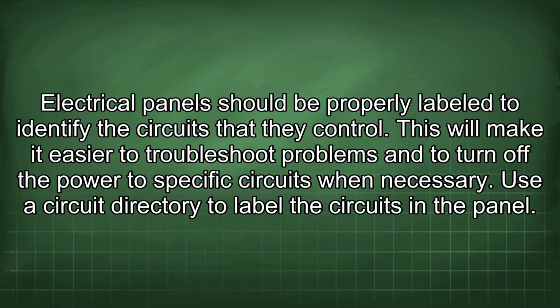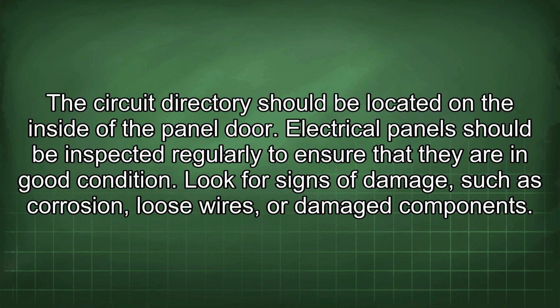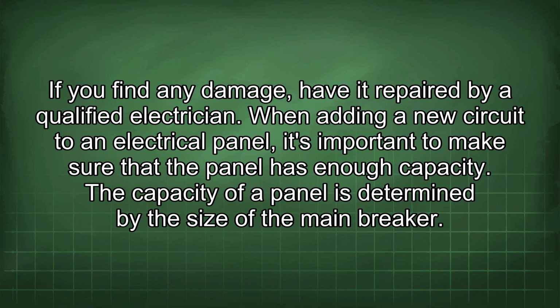Electrical panels should be properly labeled to identify the circuits that they control. This will make it easier to troubleshoot problems and to turn off the power to specific circuits when necessary. Use a circuit directory to label the circuits in the panel. The circuit directory should be located on the inside of the panel door. Electrical panels should be inspected regularly to ensure that they are in good condition. Look for signs of damage such as corrosion, loose wires, or damaged components. If you find any damage, have it repaired by a qualified electrician.